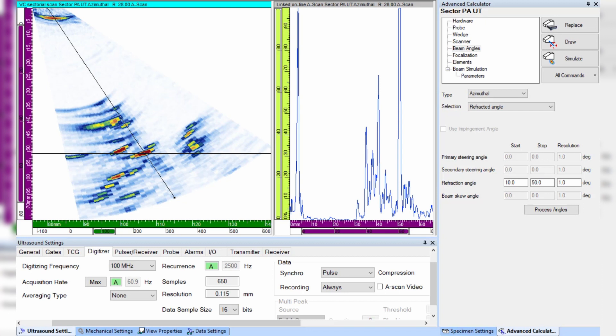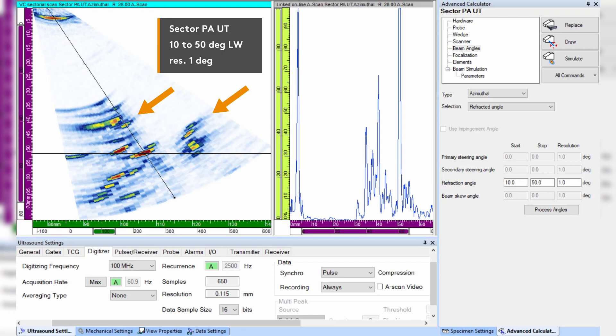In this video we will be looking at ultrasonic images of two branched cracks, at first with standard phase array from a 5 megahertz probe generating L waves using a typical sweep from 10 to 50 degrees with a one degree resolution.